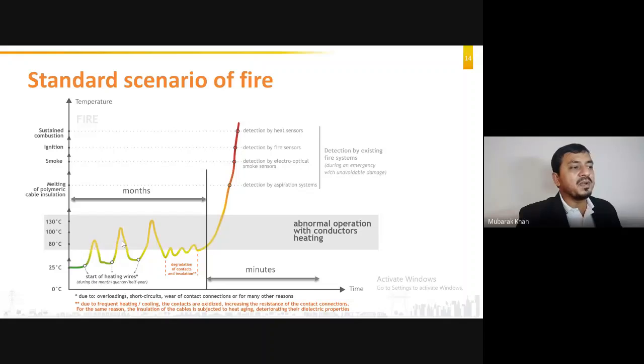So it will keep on repeating multiple times throughout the life cycle of the equipment, coming to a point eventually when the contacts and the insulation are degraded. At this point, in case of overload, the joint temperature will start to increase. It will cross 80, 100, 130. It will go to a point where your polymeric cable insulation will start to melt. Then there will be smoke. If the temperature increases further, the PVC insulation will burn. It will cause smoke. It will cause ignition. Fire will occur, and sustained combustion will be there.